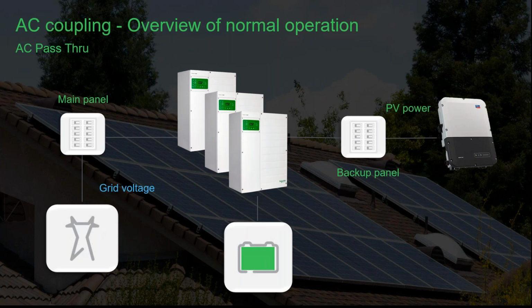Now let's have a look at modes of operation. First, let's start out with AC coupling, where a 3-phase PV inverter is located at the backup load panel. This visual shows grid voltage passing through the XW Pro, battery full, and allowing PV to add power to the AC bus. Any excess power will flow toward the main panel. Any remaining power will flow back to the grid.